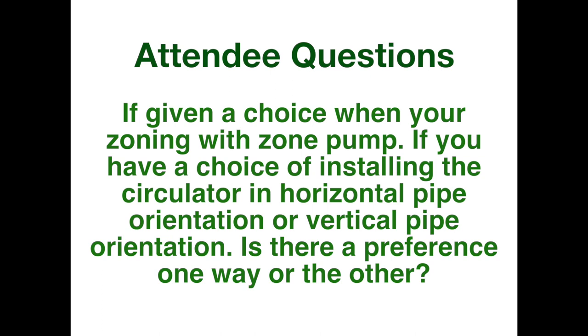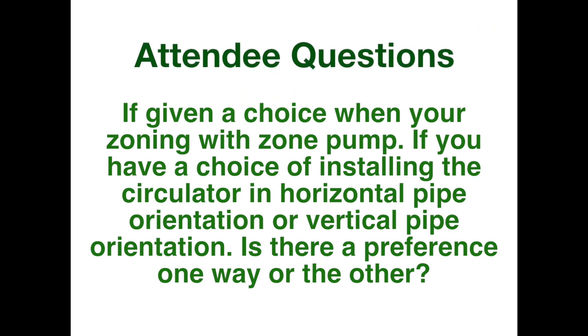I don't know what the pump people's opinion on that is. I didn't have that issue come up until we started putting those check valves right in the pump. Now, if the check valve was 6 or 8 inches away, in a separate, remote, external mounted check valve, you'd have that piping distance that could handle that little air bubble and it wouldn't lock up in the volute of the pump.